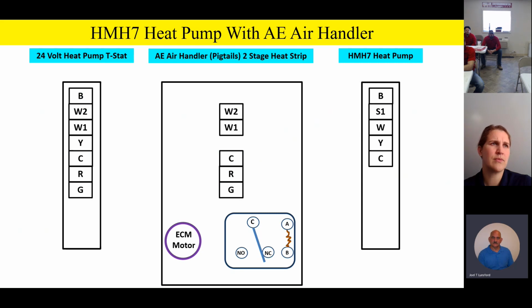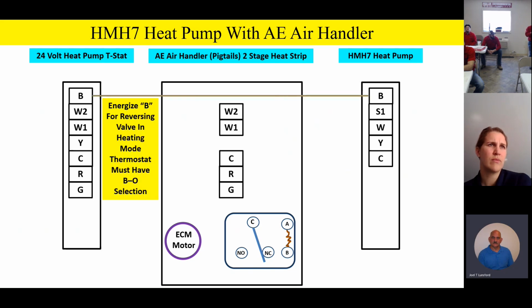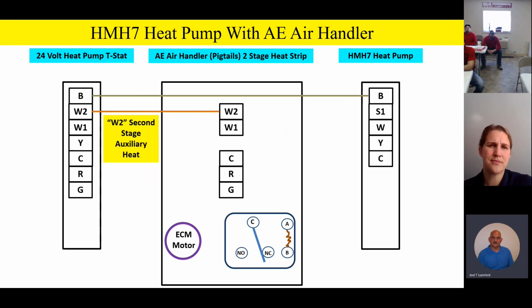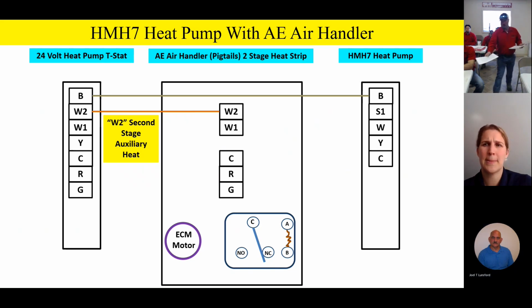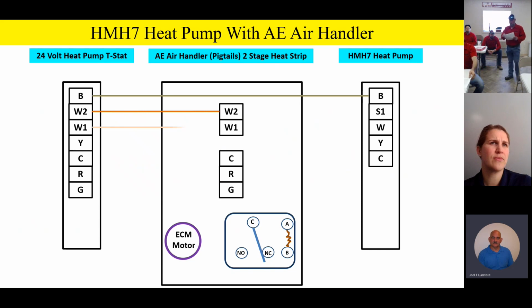You're going to notice that on the terminals themselves, we've got a heat pump thermostat on the left-hand side that does have the B capability. As we move through, you'll notice B goes from the thermostat to the outdoor unit. W2, if you have an air handler with heat strips, would be your second stage auxiliary heat, and that goes from the thermostat directly to the second stage. And on the first stage auxiliary heat, your W1 input will go all the way through from the thermostat to the indoor unit to the outdoor unit.